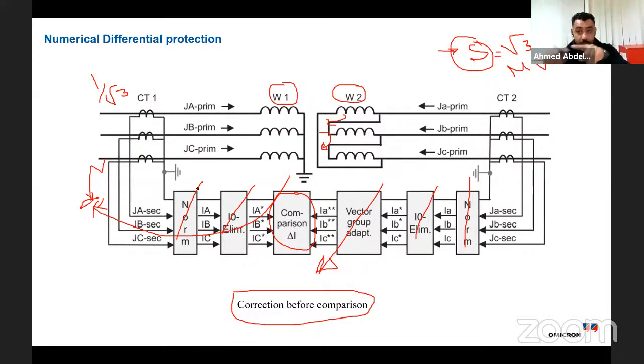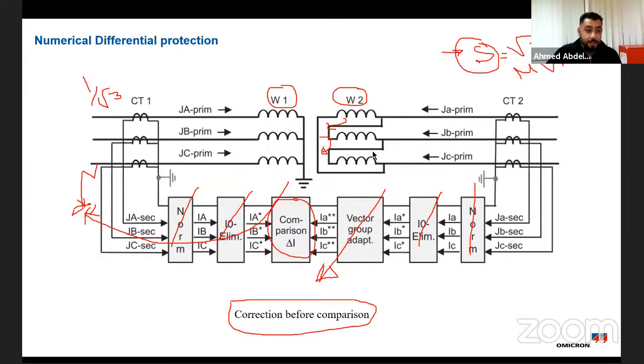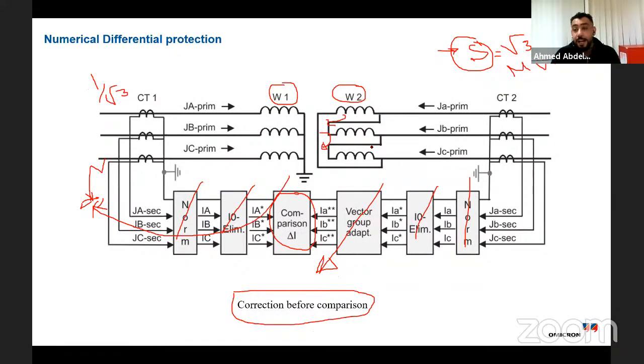We have a great table of the vector group effect: if I have 1, 2, 3, 4, the current will be lagged by an angle of 1 multiplied by 30, 2 multiplied by 30, 3 multiplied by 30. So the vector group adaptation will happen only on the delta side. Afterward, the current will be ready for the comparison. But I did this kind of adaptation based on the steady state characteristic.